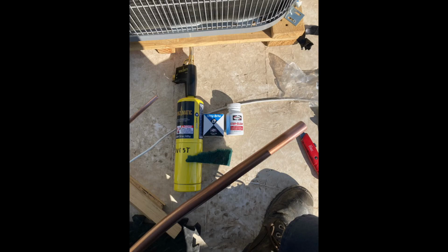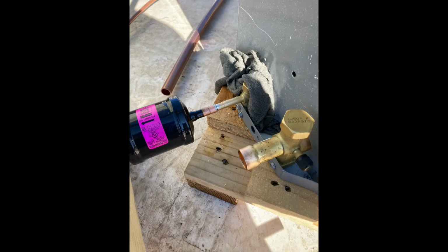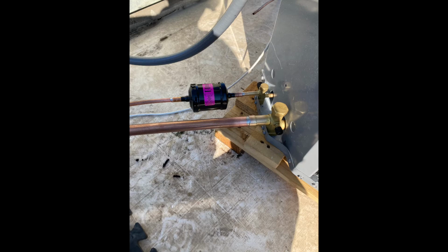And I'm using Stay Bright 8 and MAP gas to solder my connections instead of using the brazing torch and brazing rod. This is the second option I wanted to make you aware of. Stay Bright 8 is a great solder, high strength solder. So here we've soldered in the filter dryer. Next we'll solder in the suction line, and you'll note I wrapped a cold damp cloth around the service valve. There they are, both installed.